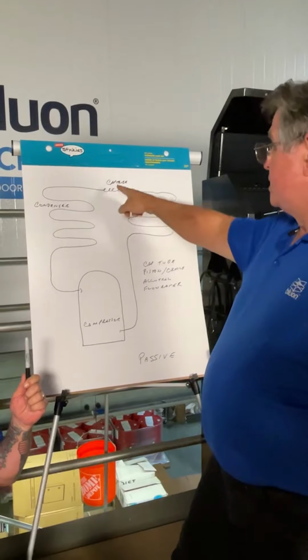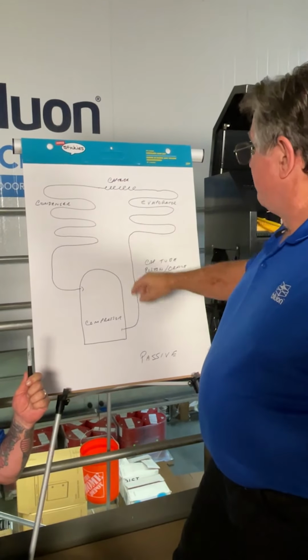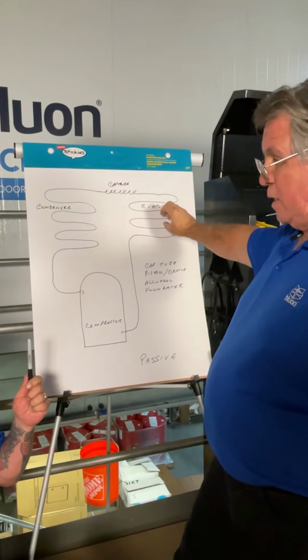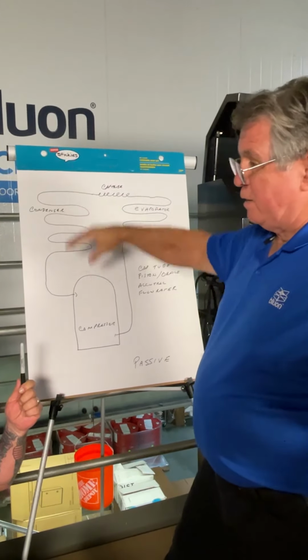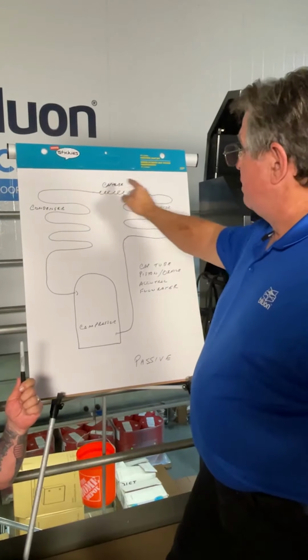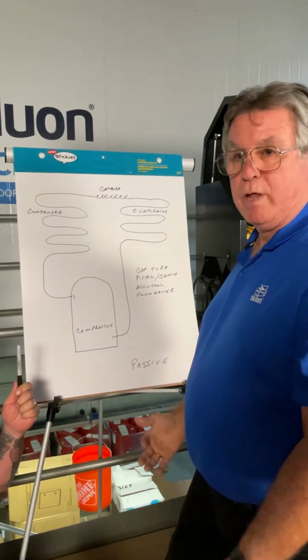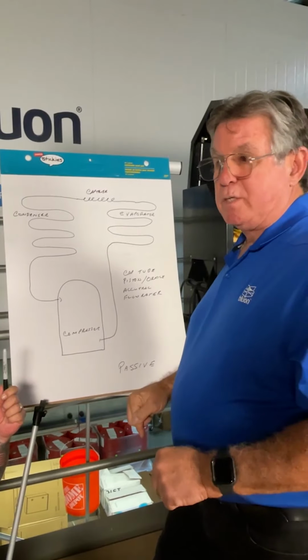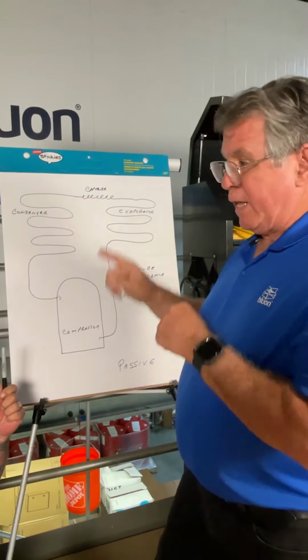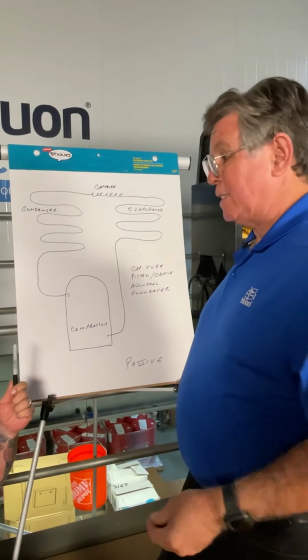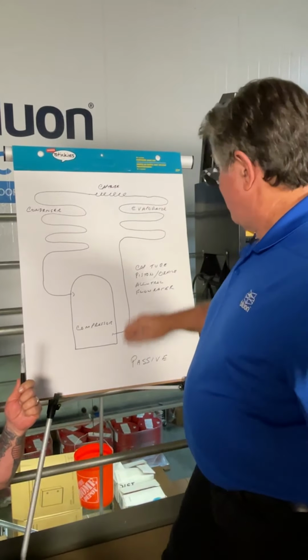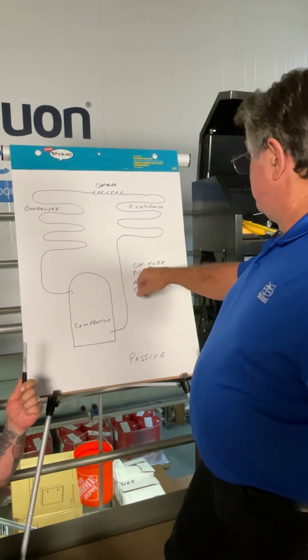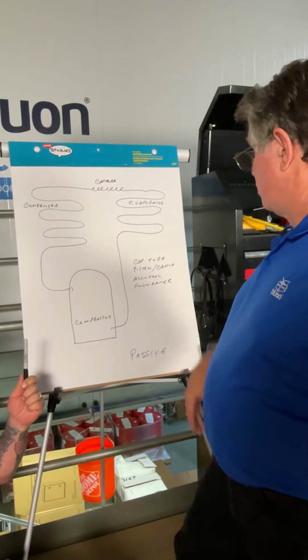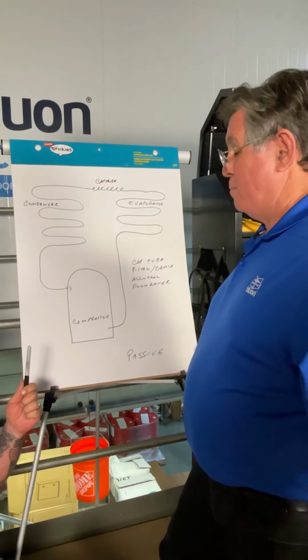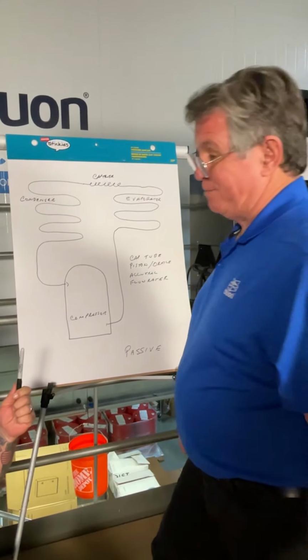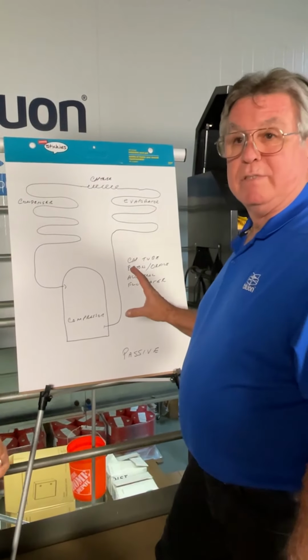Well, the thing that changes the flow through a cap tube is if this gets really cold, the pressure is going to drop. If it gets really, really hot out here and the pressure goes up, you're going to have a higher differential pressure and it's going to cause more flow. Cap tube systems are critically charged. So we've only got so much refrigerant in this system, and when we get maxed out, we don't got no more. It's all pretty much done. Cap tubes, pistons, orifices, Accutrolls, flow raters, and theoretically a manual TXV, a manual expansion valve, are all your passive devices.